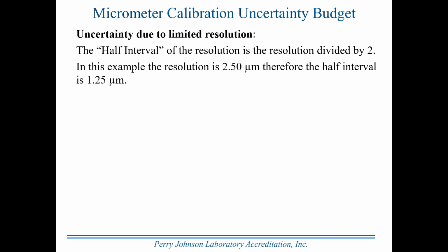Now we might measure multiple times, and it's actually detecting internally a difference of a billionth of a meter. However, we can't see that on the indication, the display or the output, because it only outputs to 2.5 micrometers. So we could say, well, it might be right in the middle of that. So it's some number plus 1.25 and minus 1.25 to give us the width of the interval. But we don't know beyond that what it is within that interval.